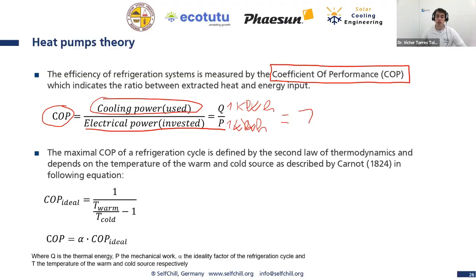But if we get 2 kilowatt hours out of the heat pump for 1 kilowatt hour of electricity, then we'll have a COP of 2. Okay, so you see how big the COP is depends a lot on how low the pressure differences are. If the ambient temperature is closer to the cooling temperature, then the pressures are low. The compressor doesn't have to compress so much, and we will have a high COP. If we have a high difference between pressures and temperatures, then the COP will be lower, okay?